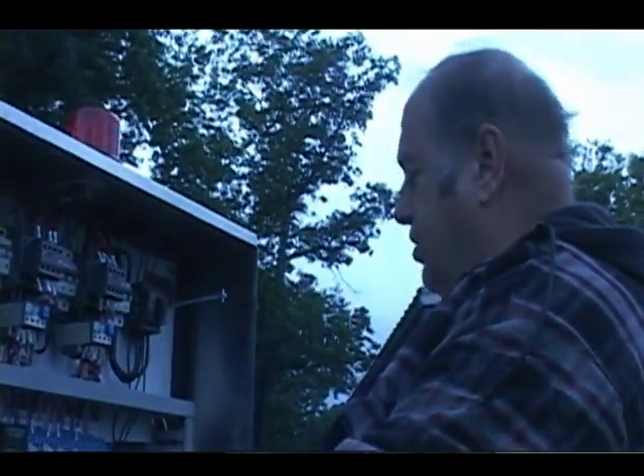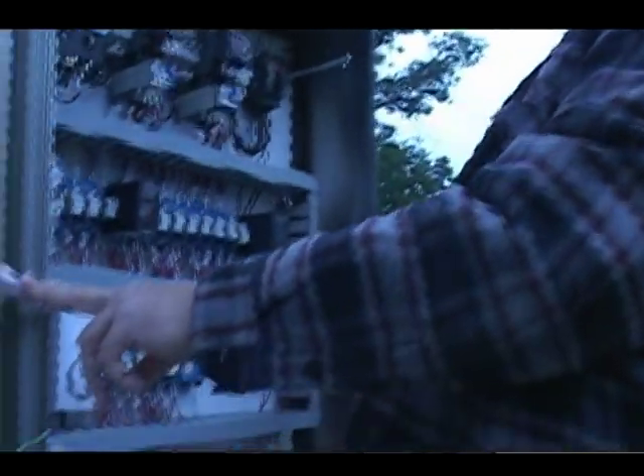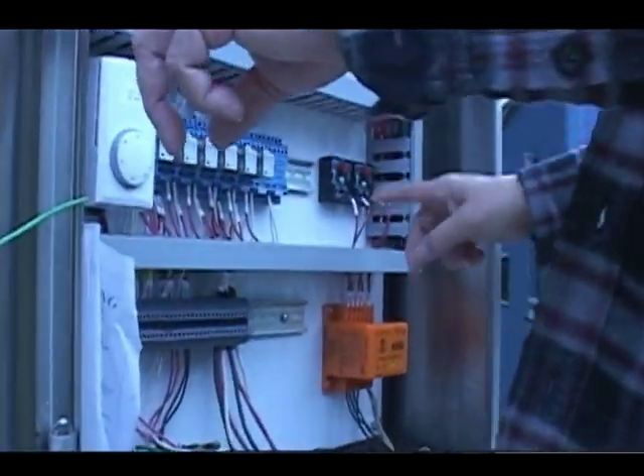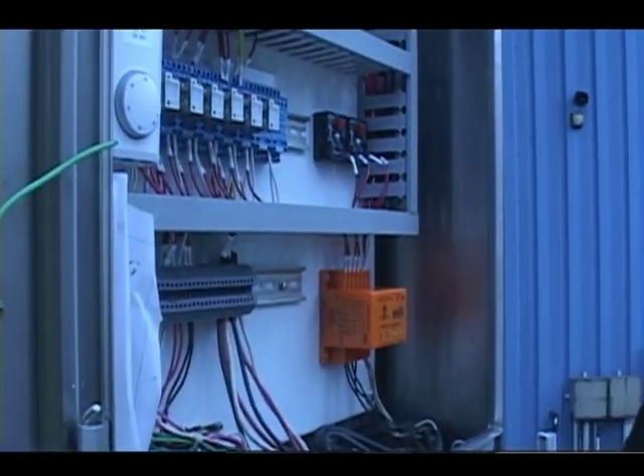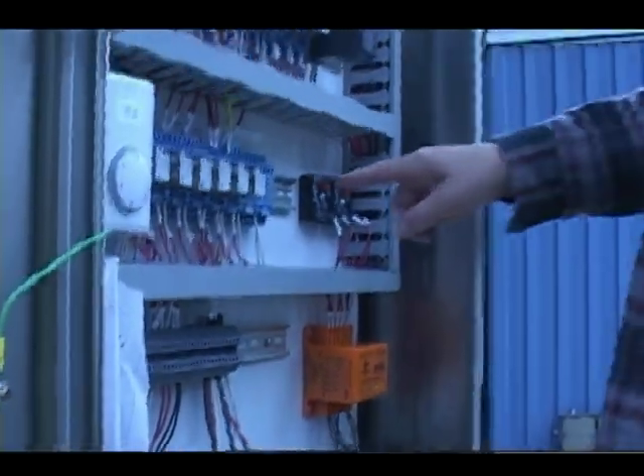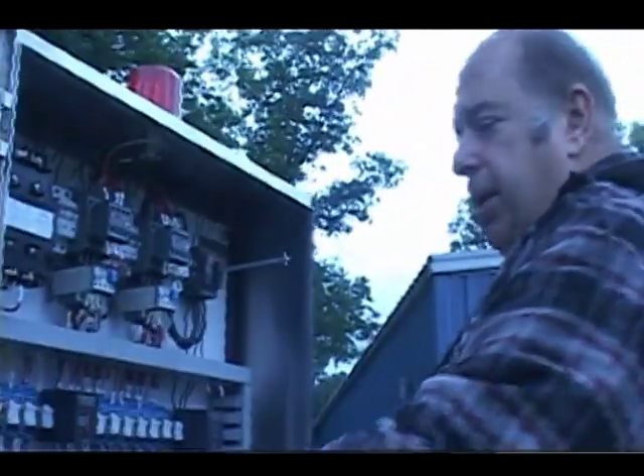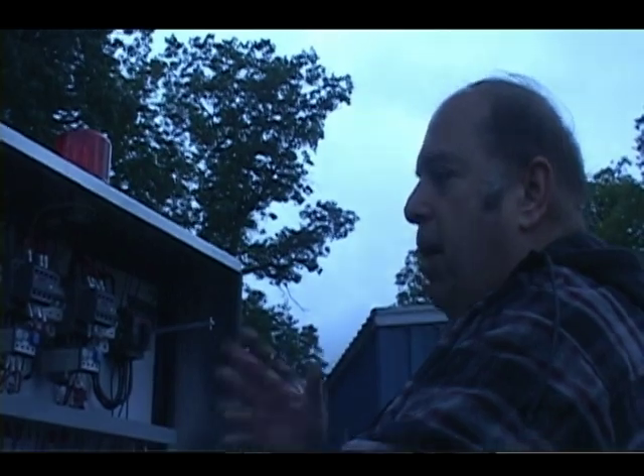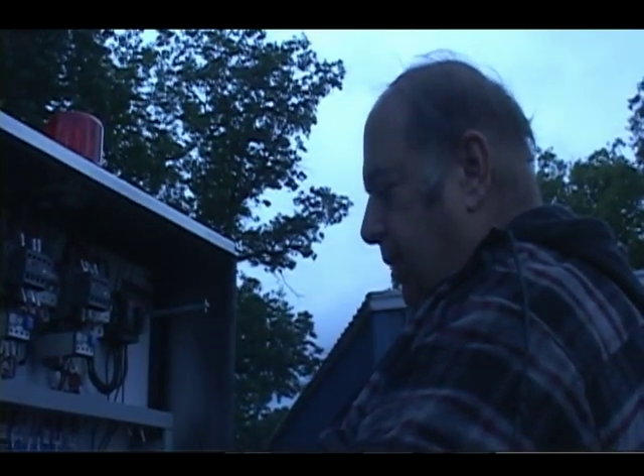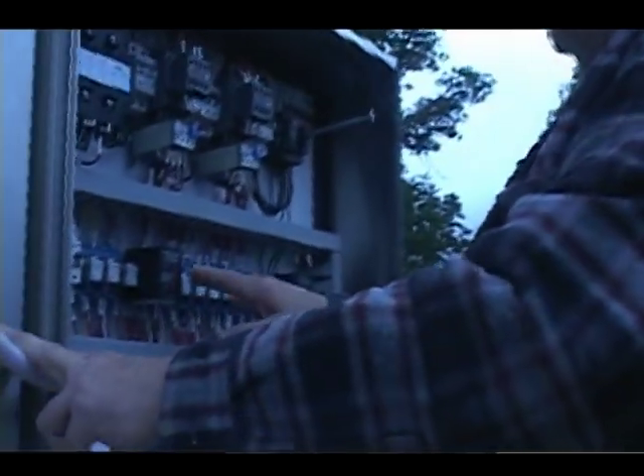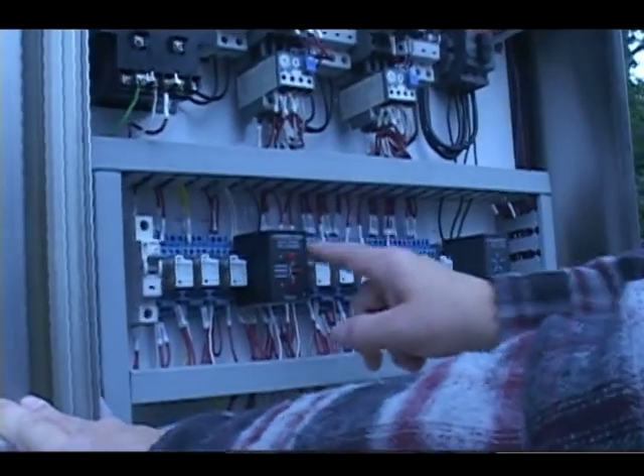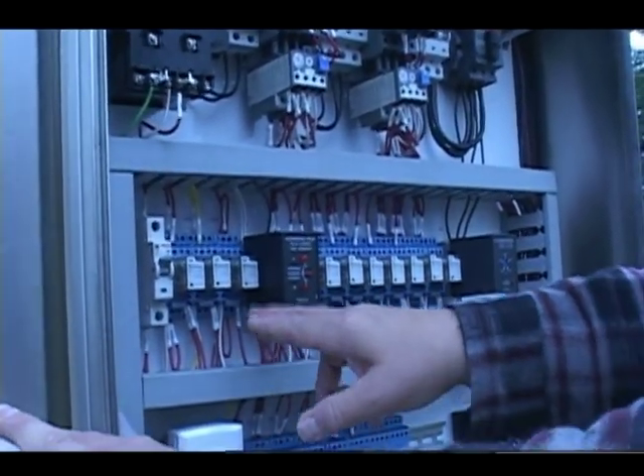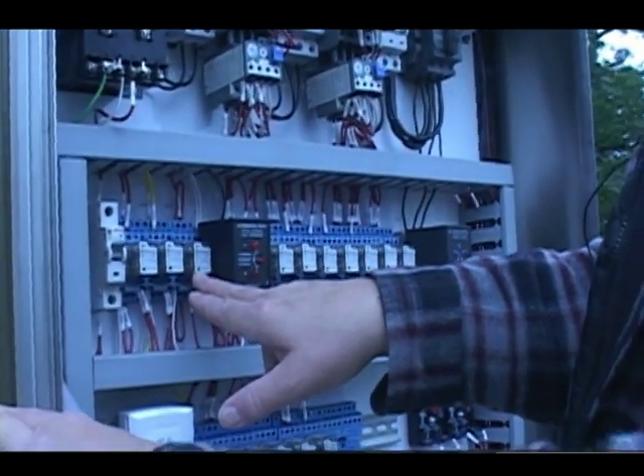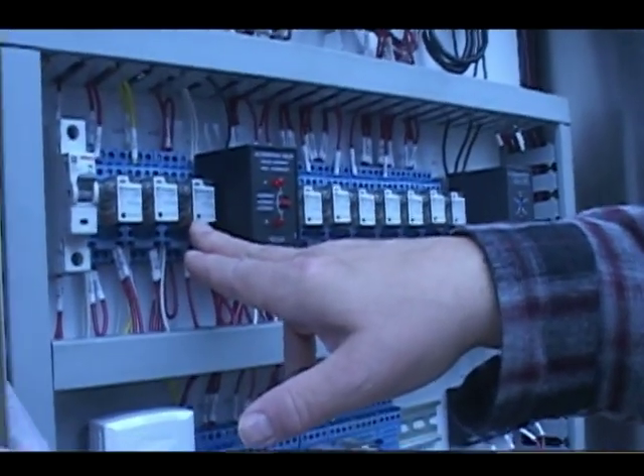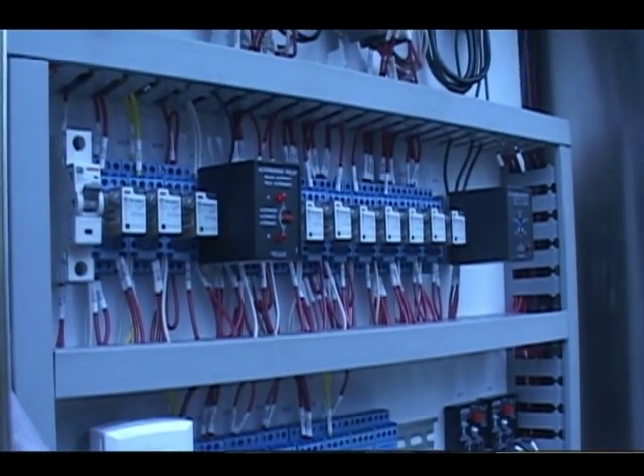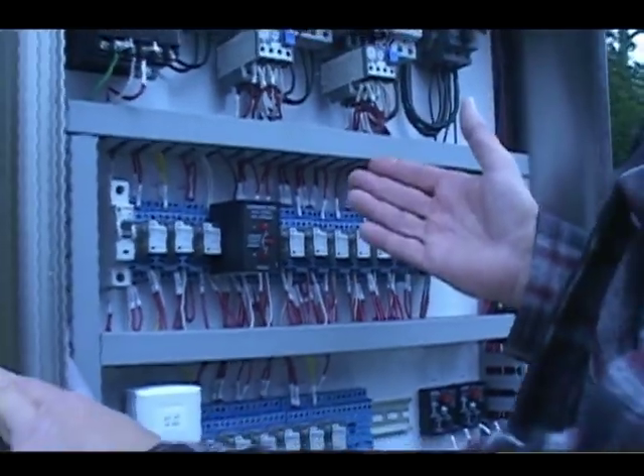Right? We also have some motor temp timers here that prevents nuisance tripping of the over temp on the motor. Normally that's when the power cycles on and off. Right? You have interface relays, which are these little finder relays, and as you can see, they all have little indicating lights on them to say that they are powered. That tells you there's 110 volts to the coil.